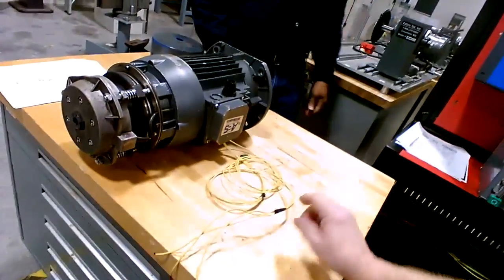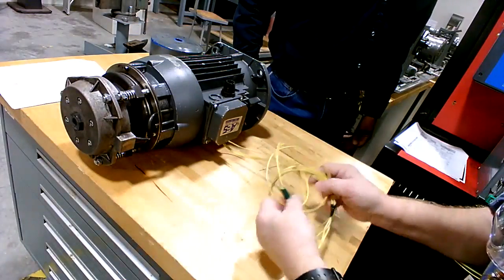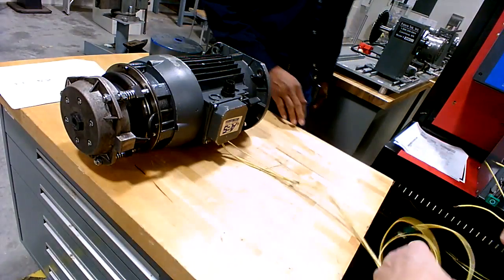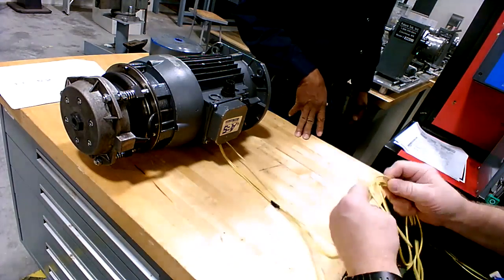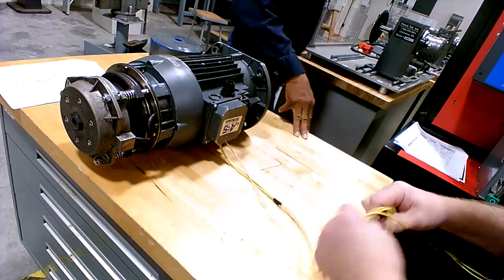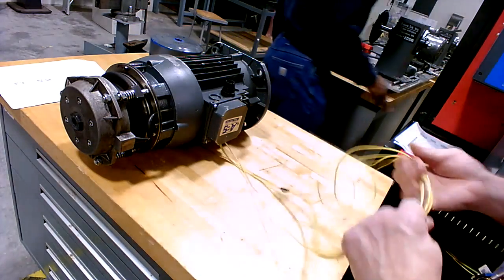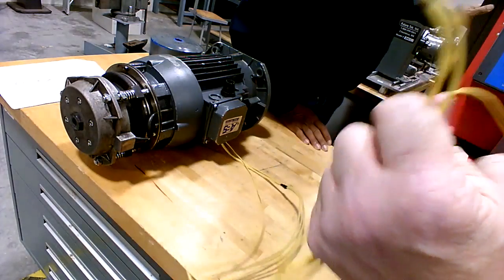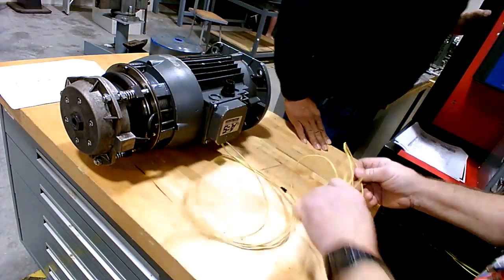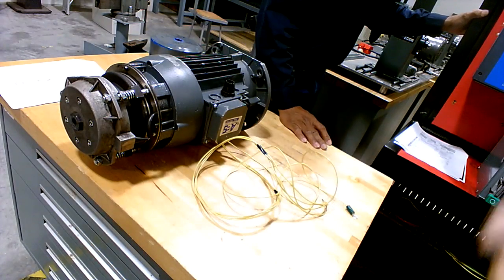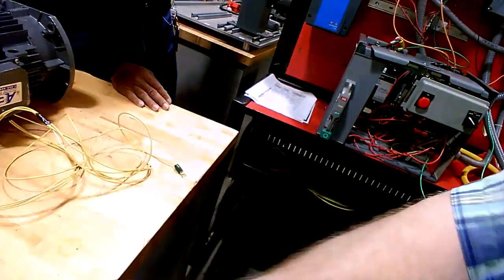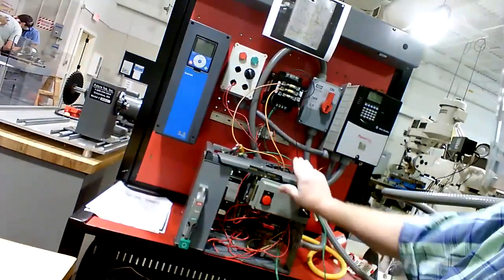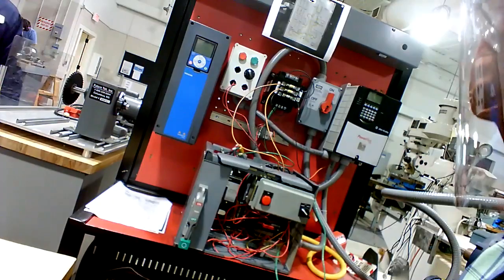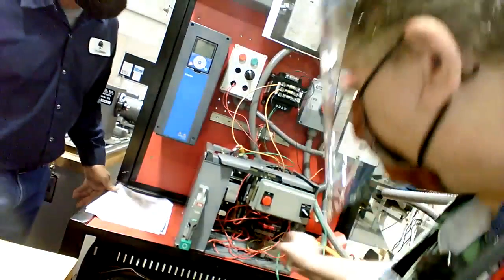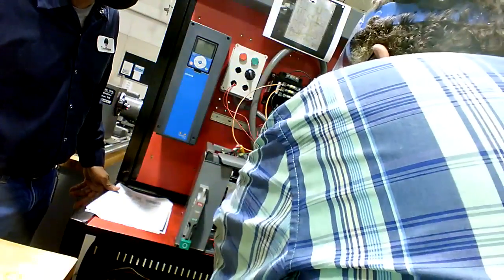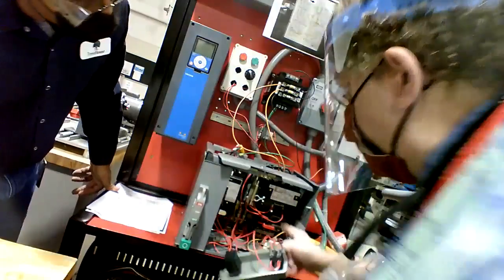So we're going to wire this motor here. It's a 3-phase 480 volt motor, so it has three hot wires and the ground. Three hot wires here and the ground. And we're going to use something called a motor control bucket to power the motor. This bucket right here actually came from the Butterball plant, and we're going to tie to a motor starter that's in here.